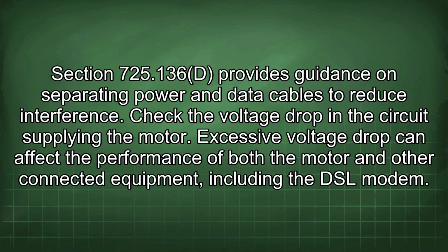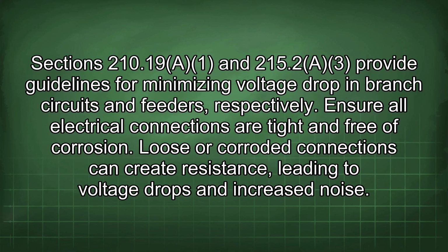Check the voltage drop in the circuit supplying the motor. Excessive voltage drop can affect the performance of both the motor and other connected equipment, including the DSL modem. Sections 210.19(A)(1) and 215.2(A)(3) provide guidelines for minimizing voltage drop in branch circuits and feeders, respectively. Ensure all electrical connections are tight and free of corrosion. Loose or corroded connections can create resistance, leading to voltage drops and increased noise.